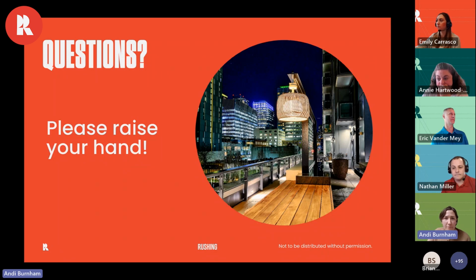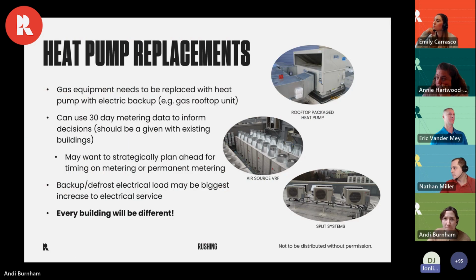Dwayne, I see you've got your hand up. Yeah, thanks. I just wanted to add: before you do a big system replacement with a heat pump, get some metering on it and find out what your actual peak loads really are. For space heating, you might have double the capacity you really needed. For water heating, it might be 10 times the capacity you really need based on old rules of thumb.